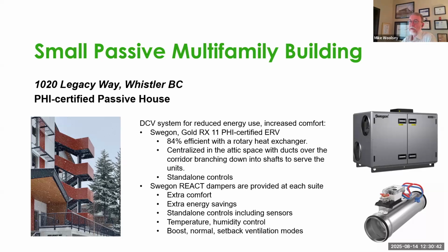So it's one of those things where you get what you pay for. It's true a constant airflow damper costs less, and I understand they seem like an easy quick fix for airflow control. But when you use something more like this - one of our react control dampers - it has its own controls. It's a product concept that's been on the market for decades, able to give you extra energy savings. For instance, if you leave the apartment, the occupancy sensor can turn off the airflow or turn it down to some minimum, and there's a lot of energy saved there thanks to giving the fans and ERVs a break.